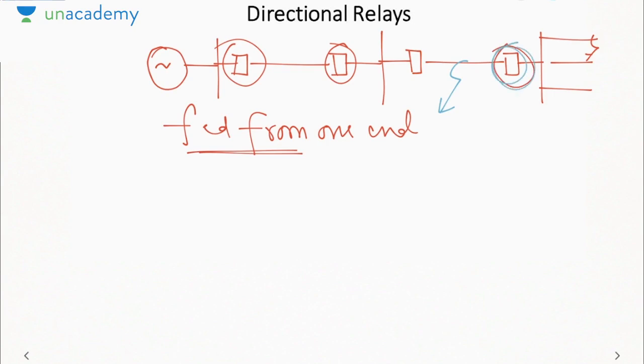Then this relay will not be getting any current. The entire current will flow like this. So definitely this will operate first of all. If fault occurs here, current will flow like this. So this will operate first of all. So other relays are not affected. That means the relay nearest to the fault will operate all by itself. Is it fine? So there is no conflict of operation between the different relays.